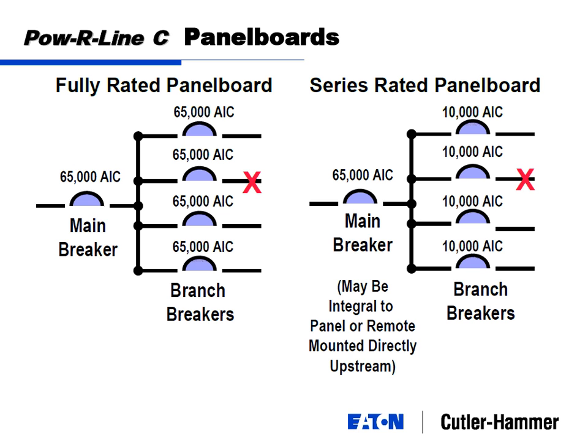Circuit breakers themselves, as the fault starts to propagate, when you start to ramp up from 100 amps up to 65,000 amps, as the fault's getting worse, circuit breakers are inherently current limiting. The contacts of the circuit breaker are going to start to open, and they're going to begin the tripping process while your fault current is still rising. And as those contacts are starting to open, you get a little arc between those contacts of 65,000 amps. That arc is traveling through air, so you're actually adding a little impedance inside there, therefore lowering the value.